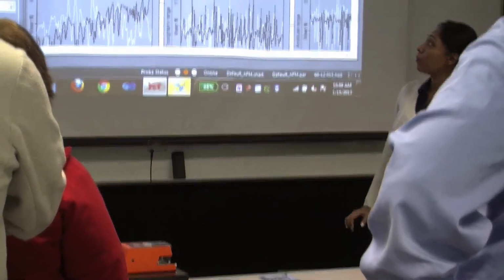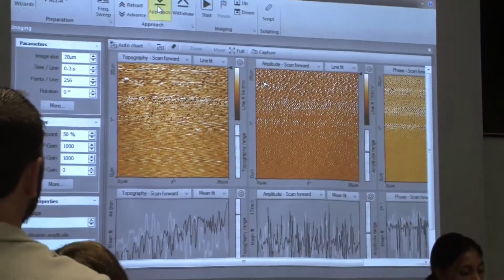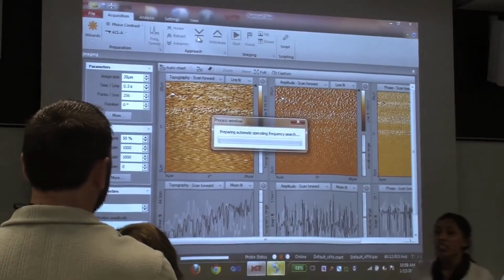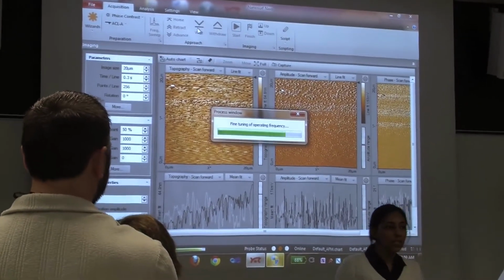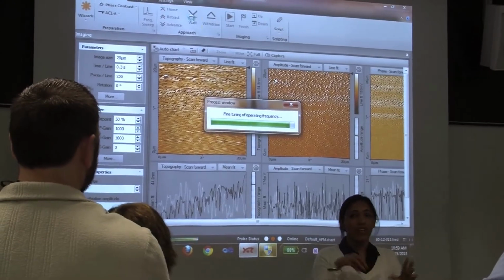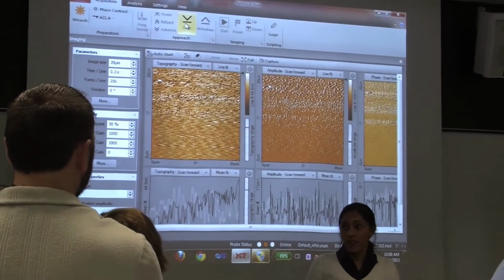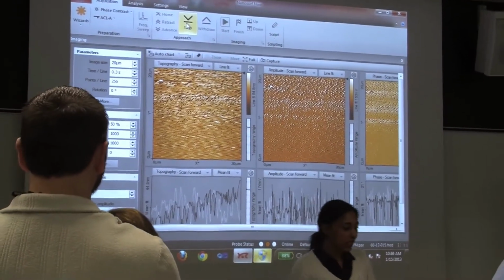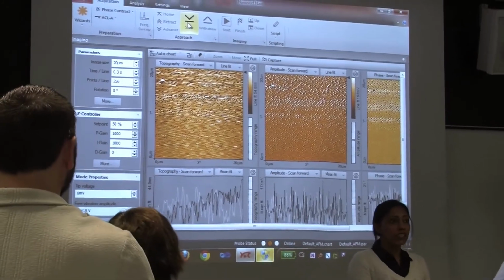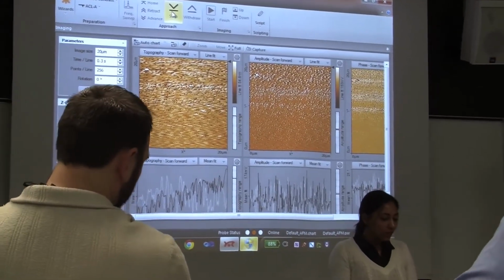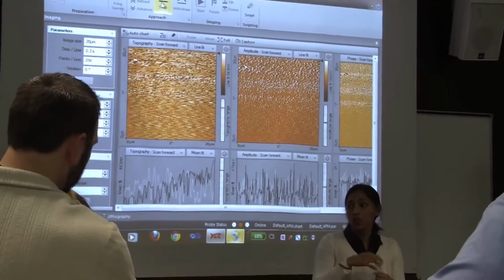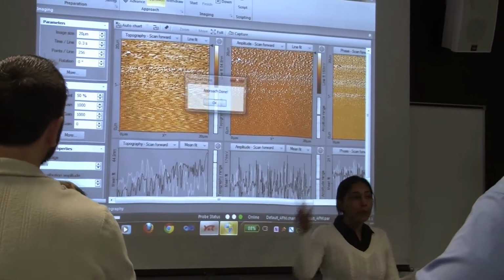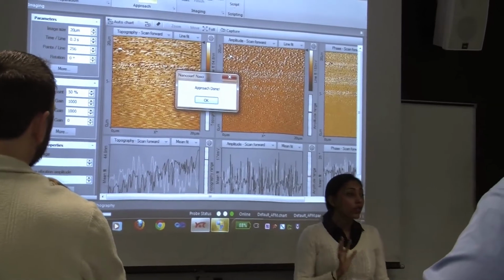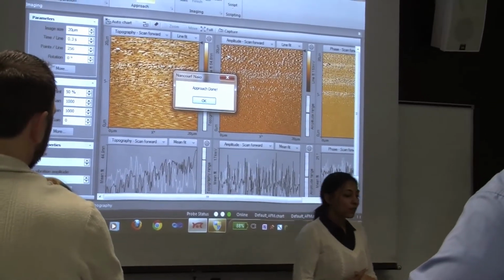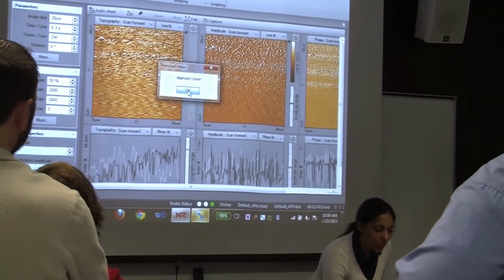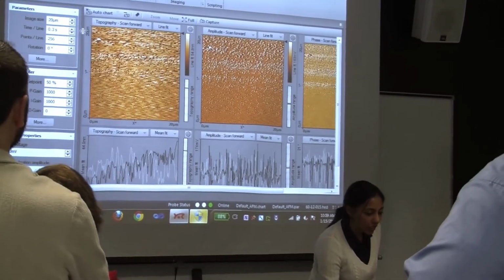So this approach button right here is for approaching my tip to the sample. Now, we cannot do this manually because it has to be very precise, and human beings are simply not that precise because we're working at the nanoscale. So the software does it for you, and it'll bring the tip as close as we want to the sample, and there's a feedback loop in there which tells it when to stop and when not to stop. So this procedure is quite slow, but okay, approach is done, and let's start imaging then.